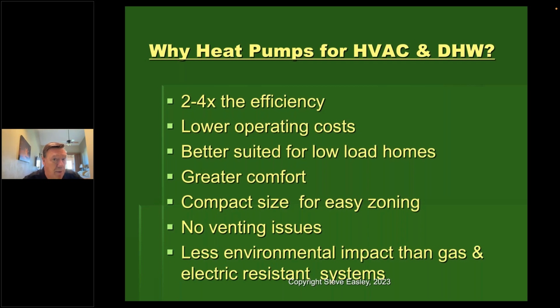So the bottom line is, why heat pumps for heating and cooling and domestic hot water heating? One, they're 2 to 4 times the efficiency. They can have lower operating costs, depending upon your local utility rates. They're certainly better suited for low load homes. As we make our homes more energy efficient, we tend to have equipment that is kind of oversized. And the beauty of variable speed heat pumps is that you're not quite so worried about them being oversized, because they know the temperature of your house, that you set what you want your temperature to be, they know the outdoor temperature, they know what the ramp up time would be to make this happen, and so they can actually vary the speed of the compressor to your actual load.